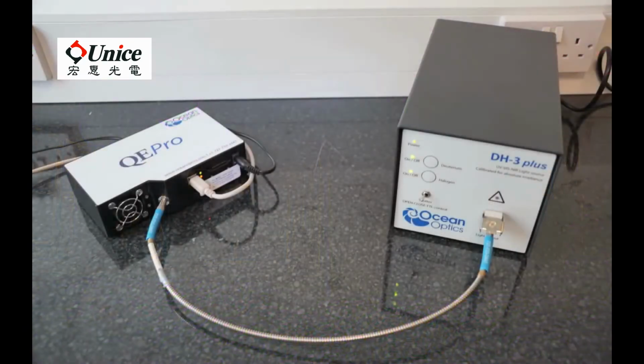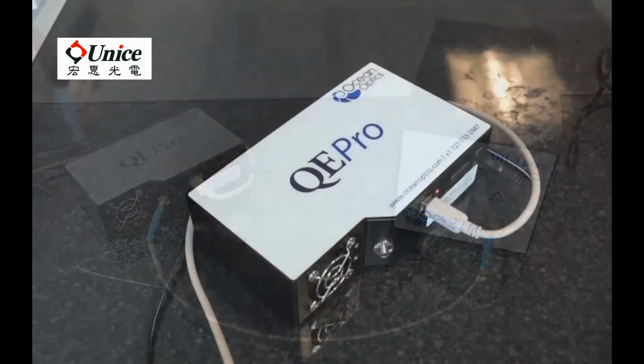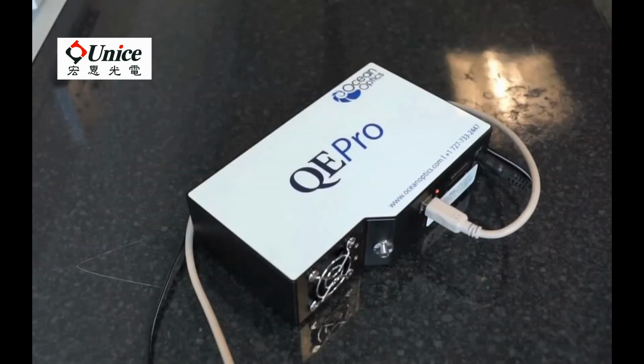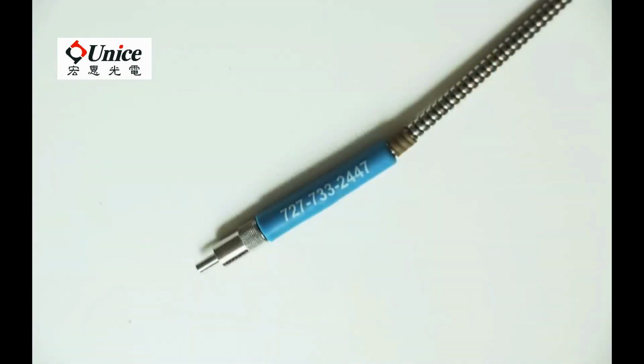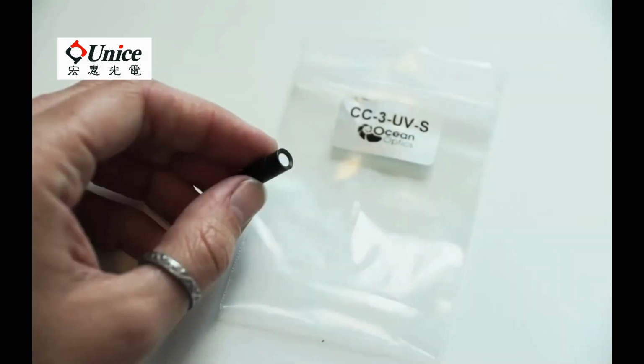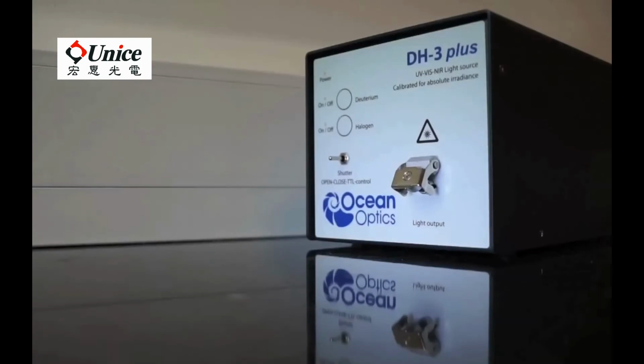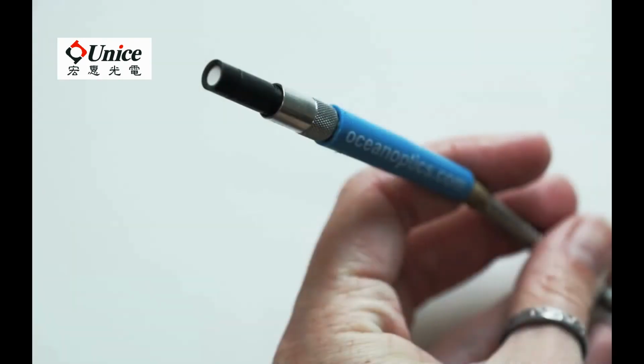The equipment we use in this demonstration is as follows. The QE Pro high sensitivity spectrometer with a 25 micron slit, a 600 micron UV vis fiber, a CC3 UVS cosine corrector, the DH3 plus calibration light source for UV vis and NIR. This is a powerful calibration source covering a wide range from 230 to 2400 nanometers. In this demonstration, we will use the cosine corrector to give a full 180-degree field of view.